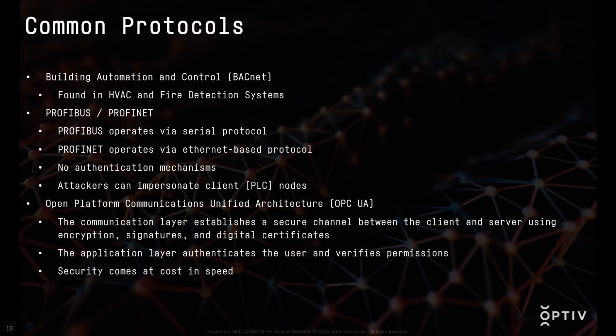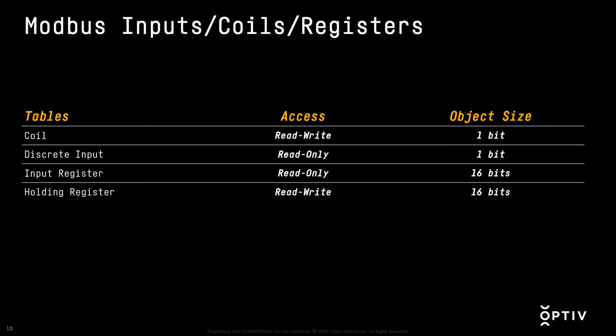But where people can get away with it, they should look at that—it's definitely a lot more secure than your older Modbus or Profinet. We're going to primarily focus on Modbus throughout this presentation, since it's still quite widely used even though it's an older protocol. Modbus really is a series of inputs, coils, and registers.